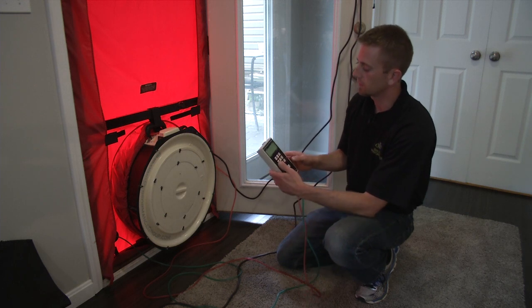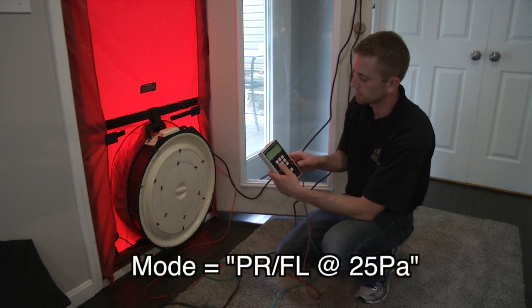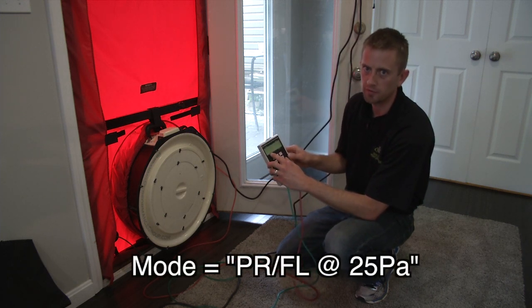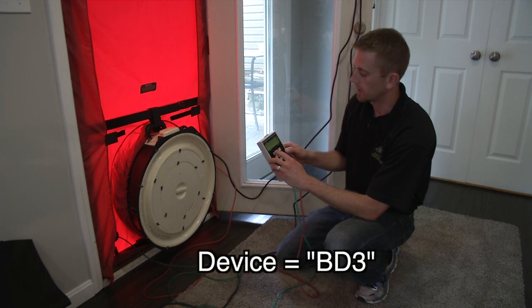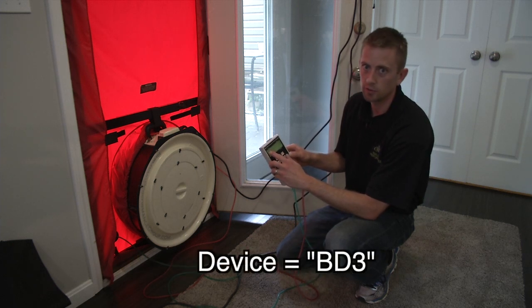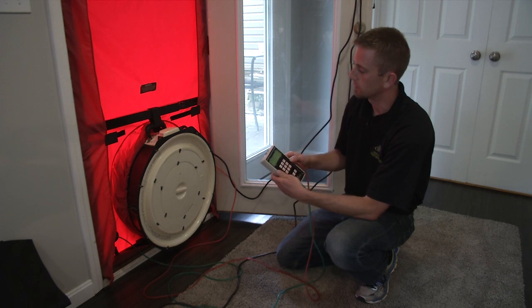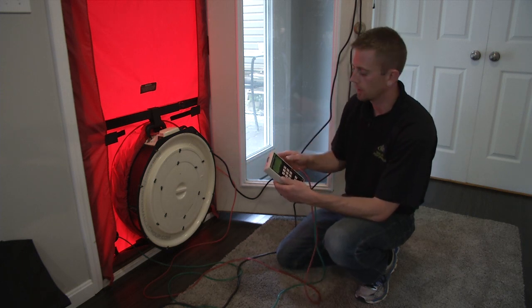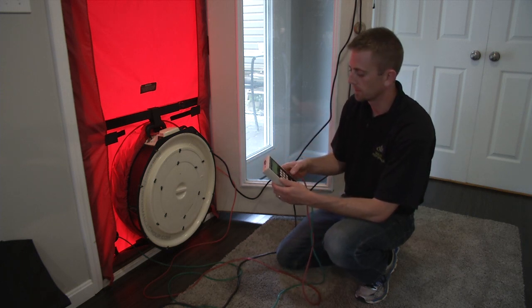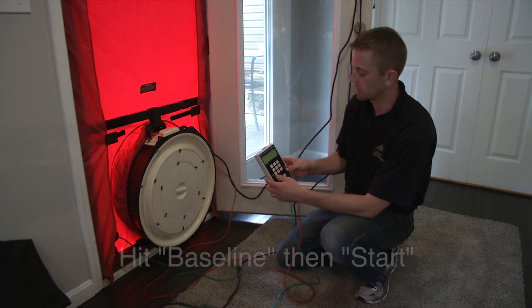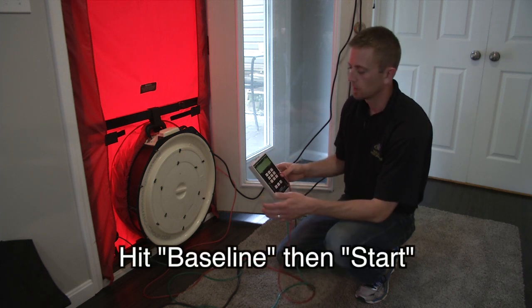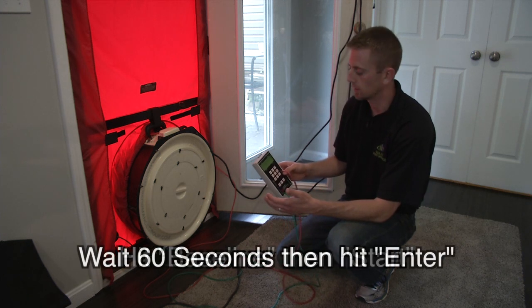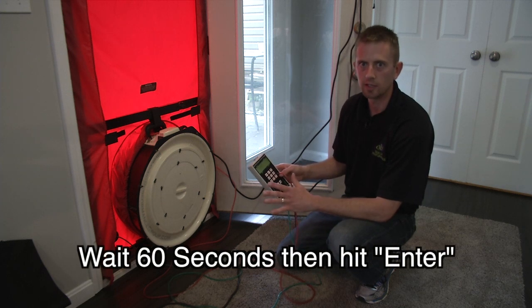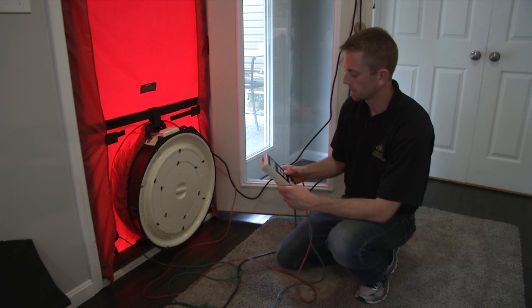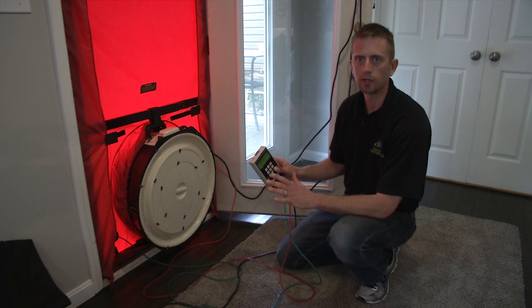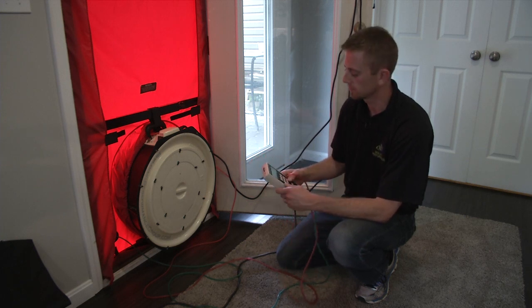So what you're going to do to set this up, you're going to hit mode until it says pressure flow at 25. You're going to hit device, it should say BD3 by default, and then you need to choose your ring setting. So I always choose ring 1, and then once you've got it set up, you hit baseline start, wait about 60 seconds. As long as it's not windy, then you hit enter. So that will get the blower door ready to go to do the test.